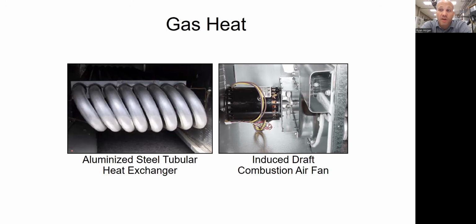Stainless steel would be if you have an owner that is going to be there a long time, like an established company. They've been there for 15 years, they know they're going to be there another 15 years, they might ask for better things, like a stainless steel heat exchanger. Or if you have an application that has a lot of outside air all the time, you might be required by the manufacturer to put a stainless steel heat exchanger in because it's condensing on there with the cold air.